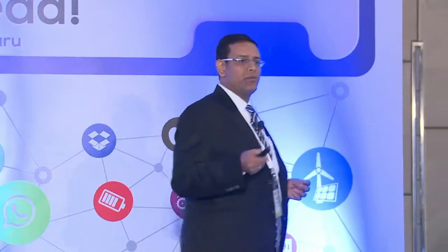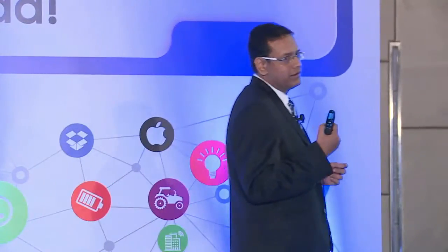At the last mile, you would see Zigbee-enabled interoperable meters, which help third-party multiple meter providers to enable a solution. At the second layer, you see a usage of sub-1 gigahertz radio technology, right, which is enabling much larger penetration across concrete. Okay? At the third layer, you're seeing GPRS or WiMAX-based connectivity to the head end, right, which is for longer range.